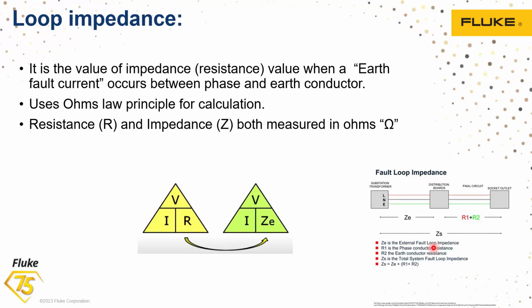A lower earth fault loop impedance means that the circuit can carry fault current more easily, which helps ensure that the protective devices operate quickly and effectively in the event of a fault. So this also reduces the risk of electric shock or fire in the facilities. Now, from the measurement perspective, the impedance we are talking about is the resistance that we are measuring. It uses the Ohm's law principle, and it uses the resistance for the calculation.